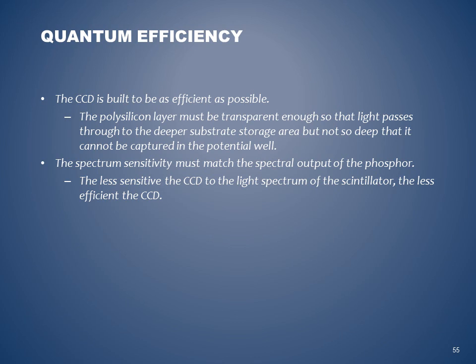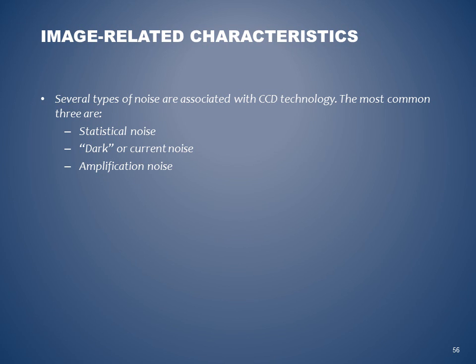Quantum efficiency. The CCD is built to be as efficient as possible. The polysilicon layer must be transparent enough so that light passes through it to the deeper substrate storage area, but not so deep that it cannot be captured into the potential well. The spectrum sensitivity must match the spectral output of the phosphor. The less sensitive the CCD is to the light spectrum of the scintillator, the less efficient the CCD. Several types of noise are associated with CCD technology. The most common three are statistical noise, dark or current noise, and amplification noise.